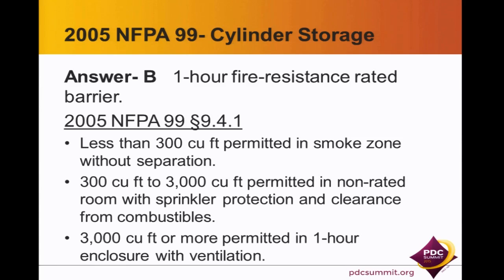And then over 3,000, of course, is the 1 hour enclosure with ventilation. That ventilation does have to be within 12 inches of either the floor or the ceiling, depending on the gases that you're storing within. So be careful not to have it at the floor when you really need it at the ceiling. And I don't think that has changed in the 2012 edition, so that answer would apply for 2012 as well.